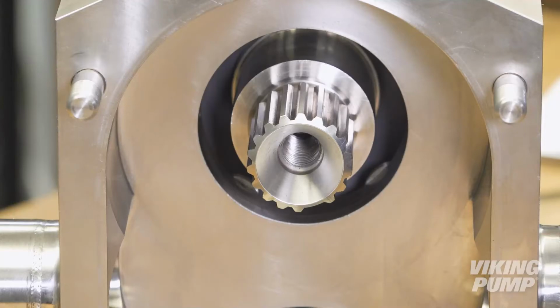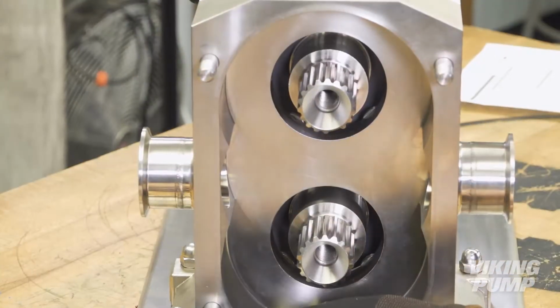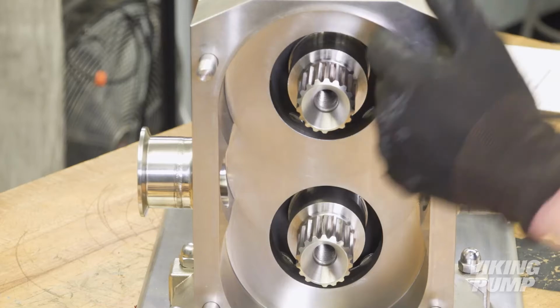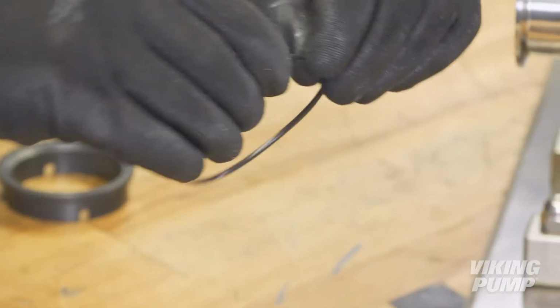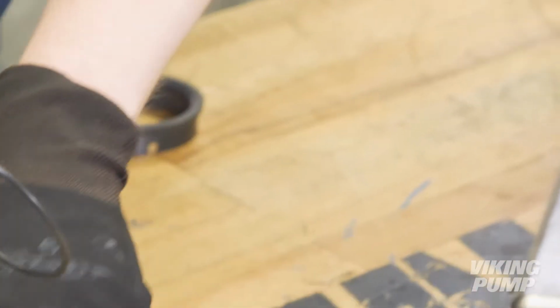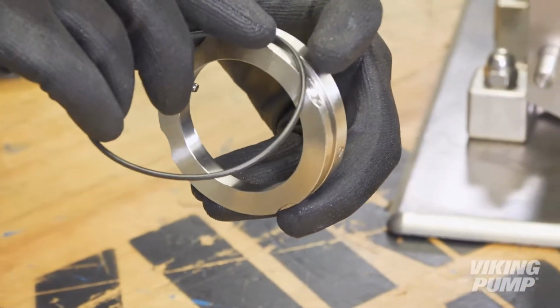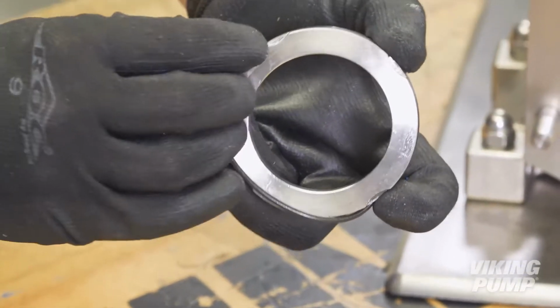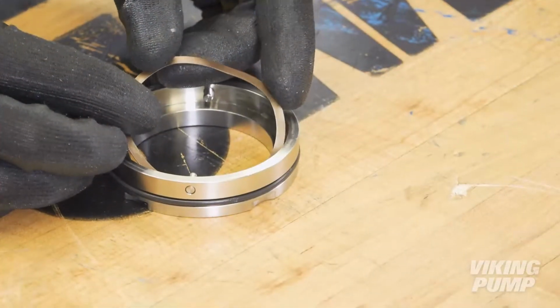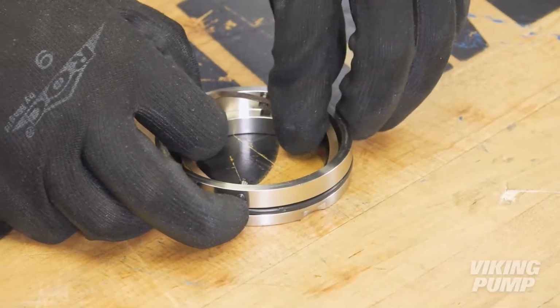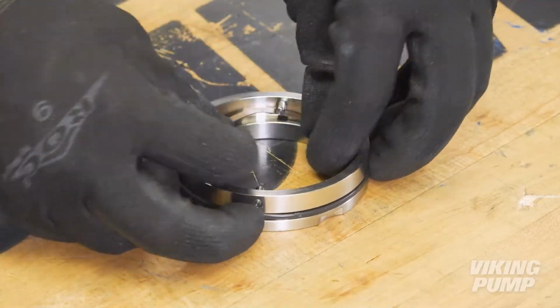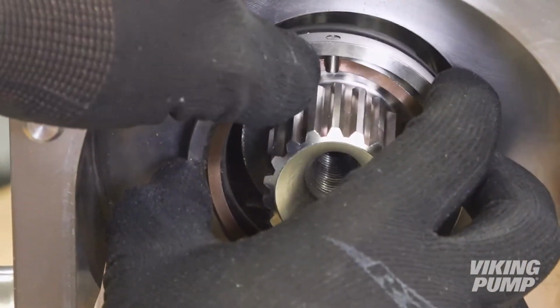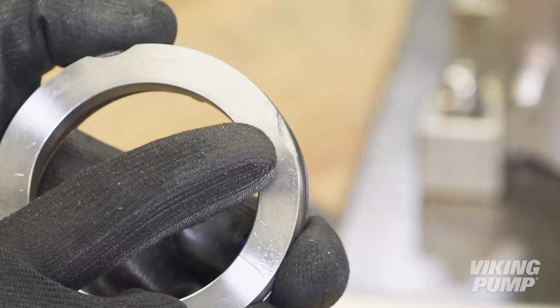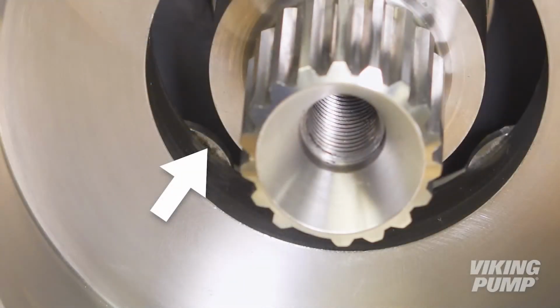Install new stationary seal assemblies. Start by inspecting the rotor case to make sure it is clean and free from debris and damage. Lubricate and install the seal housing O-ring. Install the wave spring. Slide the seal housings into each bore, making sure that the cutout recesses line up with the seal washers in the bore. Note that there is one offset seal washer to ensure proper orientation.